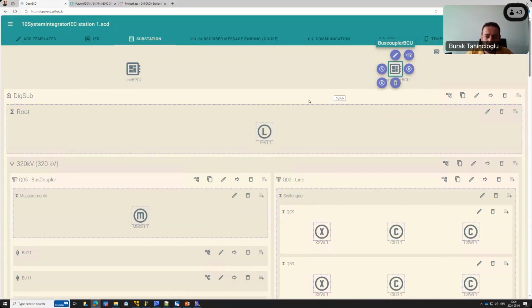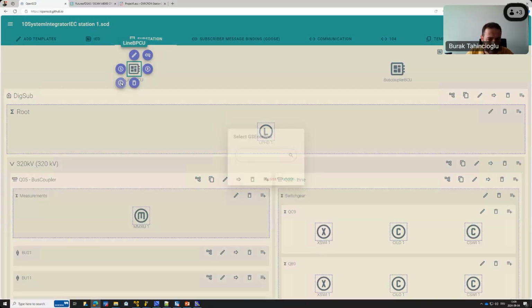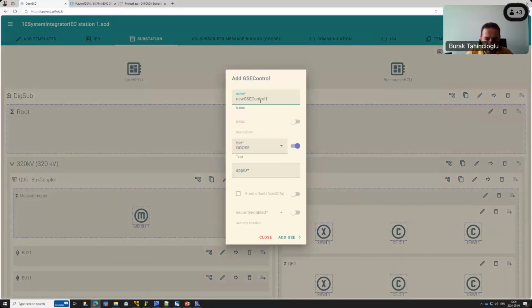I would like to engineer the communication services for these IEDs. One could be, for instance, adding one GOOSE. So if I click this GOOSE button, I can now add one GOOSE. Just name it something descriptive.